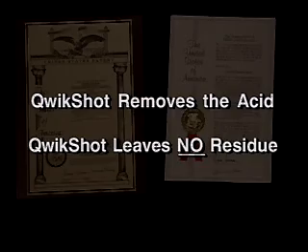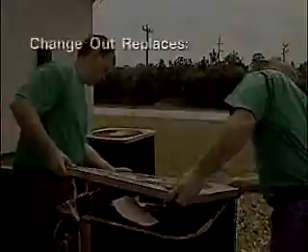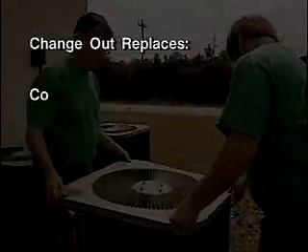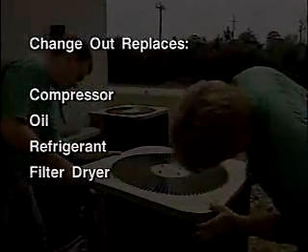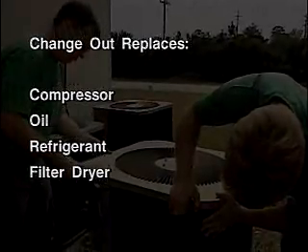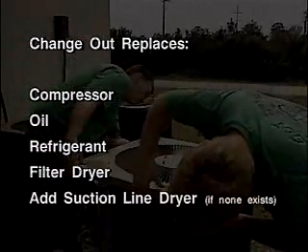All other manufacturers neutralize the acid, and that leaves a corrosive residue. QwikShot is also ideal for use with compressor burnout changeouts. The proper sequence for a changeout is to change the compressor, oil, refrigerant, and filter dryer. It is also suggested by most manufacturers to add a suction line dryer if one is not already present.